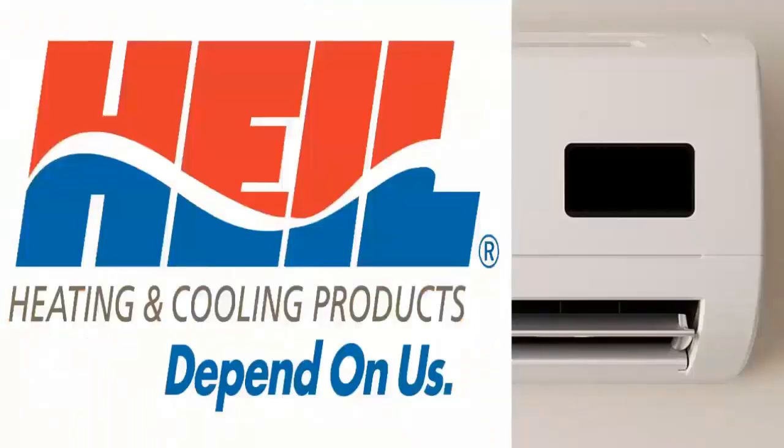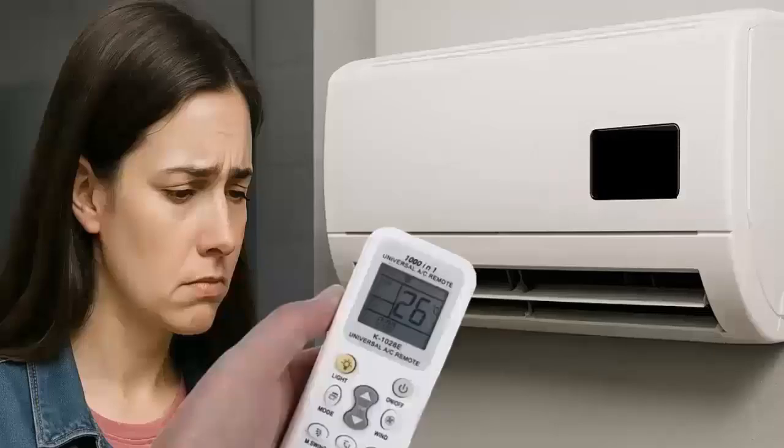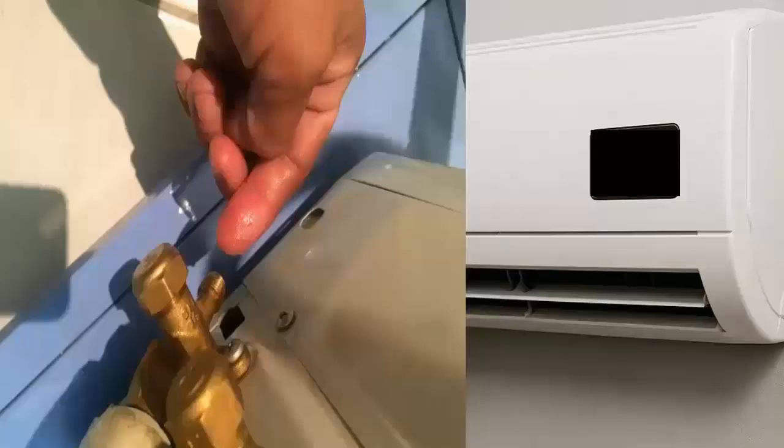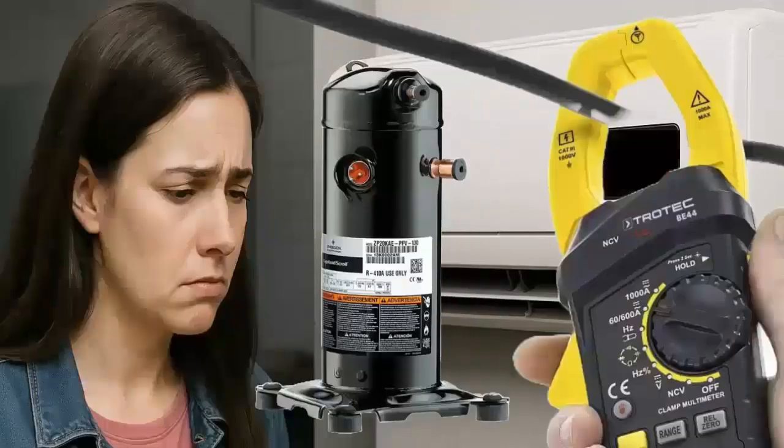What to do to fix this issue? A. Turn off and unplug the unit for a few minutes. Turn it back on to see if the error reappears. B. Look for oil stains on connections, pipes, or valves, a clear sign of leakage. C. Measure the power consumption with an amp clamp. A unit low on gas consumes less current than the rating shown on its label.